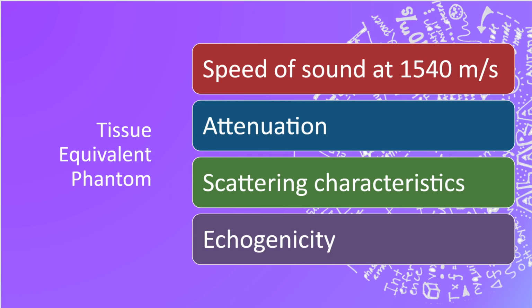Secondly, we need that soft tissue phantom to have some attenuation within it. We know that the body is going to attenuate, so we want to recreate how the sound is going to interact with an actual human. We also need to have some materials within the phantom that are going to cause reflections. So maybe little pins, maybe there's some cylinders in there. We want it to have measurable characteristics within the soft tissue phantom.